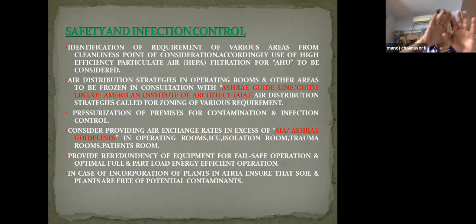Accordingly, the pressure gradient as per requirement has to be made. When we make the pressure gradient as per requirement, the air quantity also changes. Changing the air quantity also regulates the air handling unit's capacity. We should not unnecessarily pressurize an area.